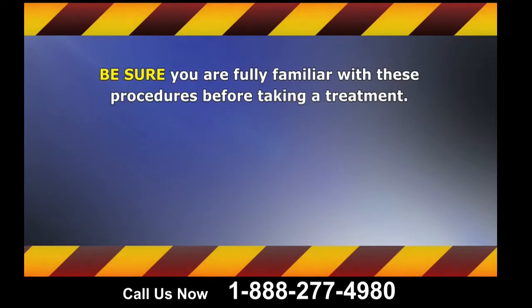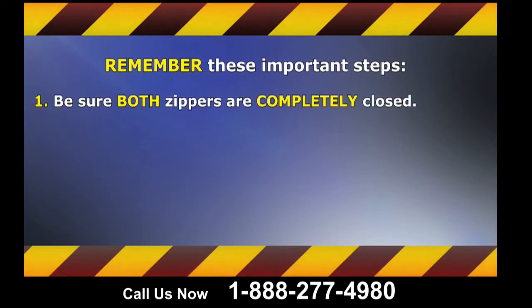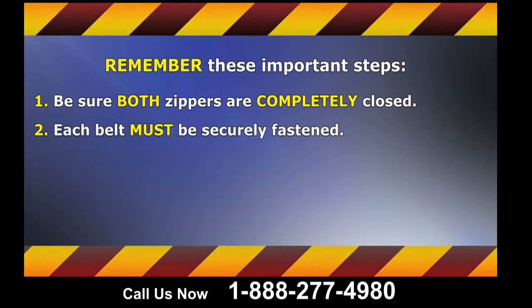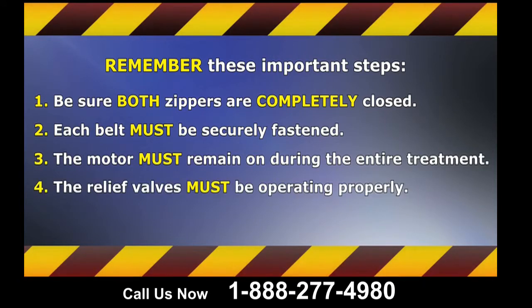Be sure you are fully familiar with these procedures before taking a treatment. Remember these important steps. Be sure both zippers are completely closed. Each belt must be securely fastened. The motor must remain on during the entire treatment. And the relief valves must be operating properly. Following these steps will ensure a safe and comfortable hyperbaric experience.